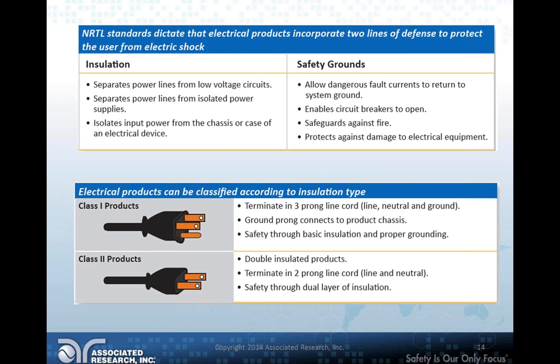A Class 1 product terminates in a 3-prong line cord, which is basically a line or hot, a neutral which is your return path for current, and a safety ground. That ground prong connects to your product's chassis, so that if something does happen, dangerous fault currents can flow back to ground without posing a hazard to you.